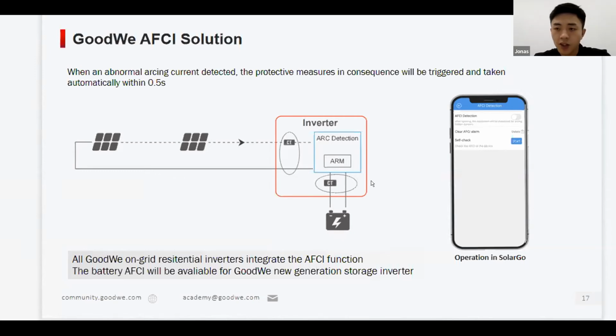At this time, there's no current flowing on the DC side, so the arc fault will be cleared. And this takes only within 0.5 seconds, so it's very safe. Let's see, this is the operation page on our configuration tool. It is called SolarGo, the configuration tool for our on-grid inverter.